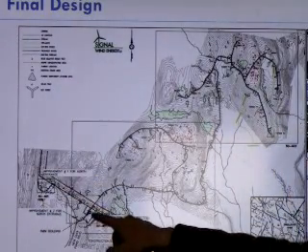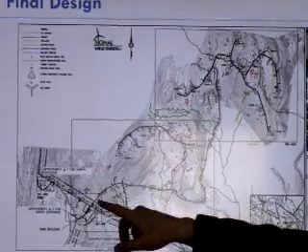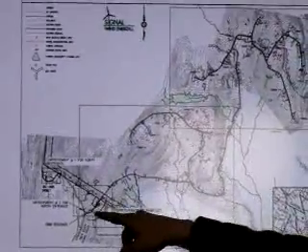You're sitting in our operations and maintenance building, which is there. The substation is right next to it. You probably saw it on the way up. All the power from the turbines, Brad, we'll get a little bit into this, is collected by what we call collection lines. The 34.5 kV collection lines are buried under the ground. They all come here, and they come to the surface at the substation.